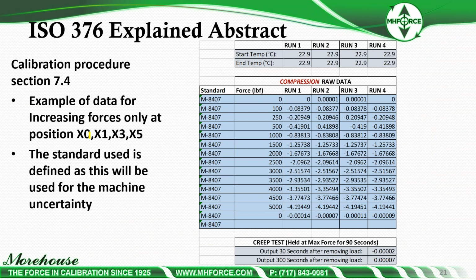So, an example of data for increasing forces only. We are at X0, X1, X3, and X5. This is what our Excel sheet looks like; yes, we are using Excel to do our 376 calibrations. We enter in all of this information: the starting temp, the ending temp, the force applied, the calibration standard over here, and the runs, run 2, 3. These are all increasing because we're doing a creep test down here. So we enter all this information in, and then we start doing data analysis.